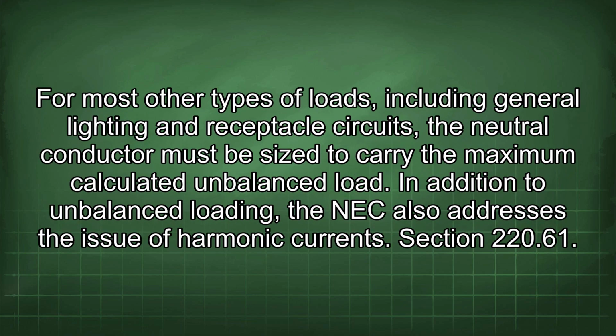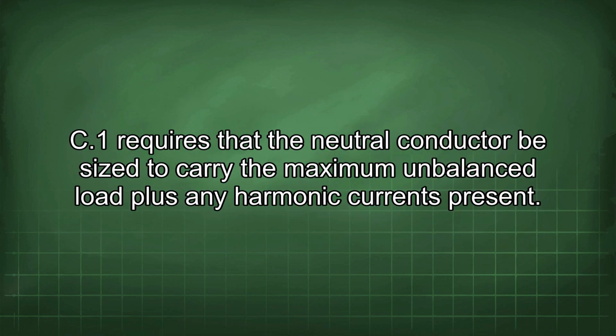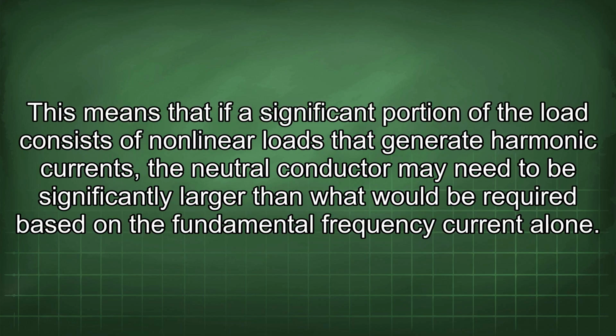For most other types of loads, including general lighting and receptacle circuits, the neutral conductor must be sized to carry the maximum calculated unbalanced load. In addition to unbalanced loading, the NEC also addresses the issue of harmonic currents. Section 220.61(C)(1) requires that the neutral conductor be sized to carry the maximum unbalanced load plus any harmonic currents present. This means that if a significant portion of the load consists of nonlinear loads that generate harmonic currents, the neutral conductor may need to be significantly larger than what would be required based on the fundamental frequency current alone.